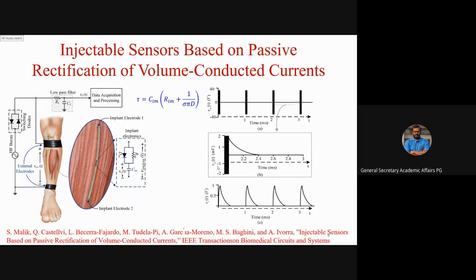So how can we charge it once it is discharged in the body? We have to charge through the external electrodes with a burst generator. We are not physically disconnecting this burst generator. There's a switching network, so it will always be there. After a specific time duration for which we have kept it on, this switching generator will automatically disconnect this node of the external electrode. We have programmed the burst generator in such a way that after a specific duration, it will turn on again, charge the capacitor, measure the specific tissue conductance, and then again. So it will keep on going.